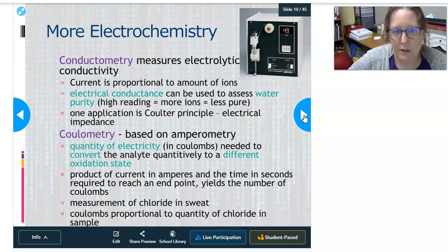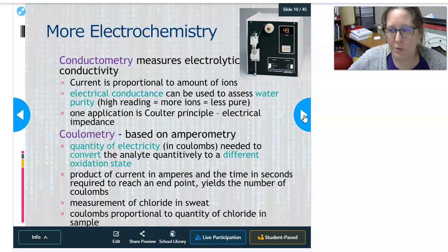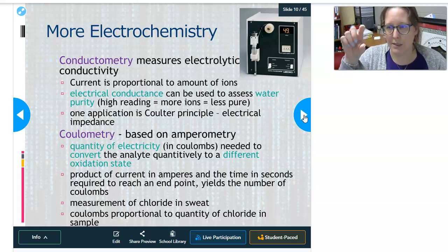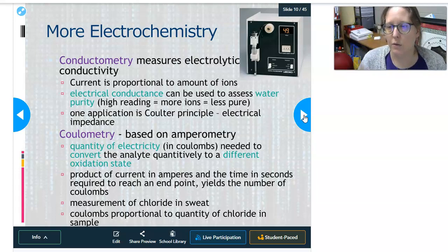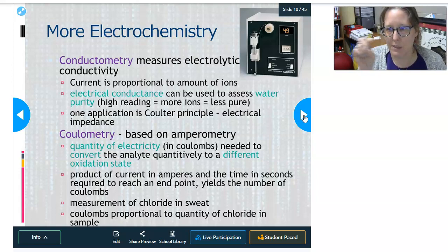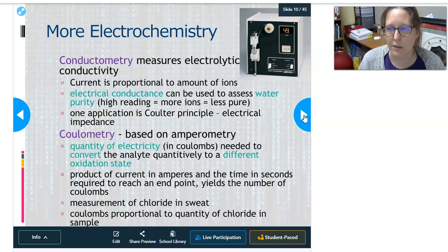One application of conductometry is the Coulter principle, which uses electrical impedance to count cells in Coulter counters or hematology analyzers. There's an aperture with a current flowing across it, and every time a cell passes through it breaks the current, counting one cell. Cells are fed single file, counted one at a time in a certain volume to get your red cell count, white cell count, and so on.